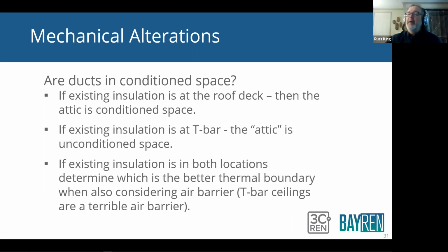So are the ducts in conditioned space? Well, if the existing insulation is at the roof deck, and the ducts are underneath that, then the ducts are in conditioned space. It's because the space that the ducts are in is more like the conditioned space than like the outside. So the insulation is at the roof deck. If the existing insulation is down below the ducts at the T-bar ceiling, let's say, then that's an unconditioned attic. You would have to seal that one.